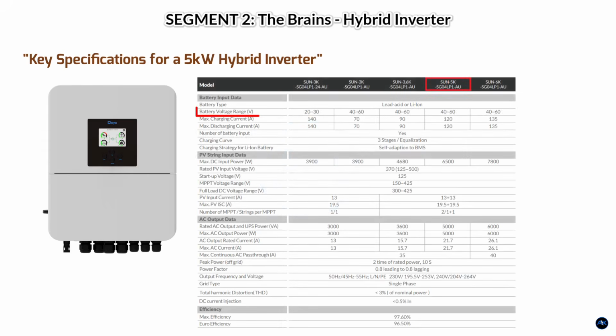Battery voltage. Common options are 48 volts. This must match your battery bank's voltage. Max charging current. How fast the inverter can charge your batteries from solar or the grid. AC output voltage and frequency. Typically 220 volts/230 volts AC at 50 Hz for most regions. Pure sine wave output. Essential for protecting sensitive electronics in your home. All good hybrid inverters offer this.